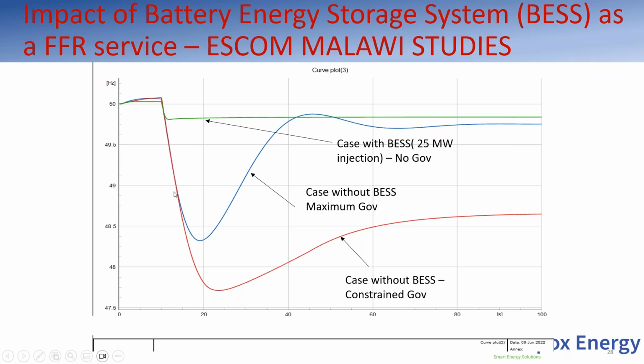But now with governing, the maximum governing here was around probably 40 megawatts, and the frequency went down to almost 48.5 for a big contingency in their grid. The contingency remains the same, so you can see the power of the battery - you don't need so much. The maximum governing here was around 40 megawatts, but with only 25 megawatts of battery, you get so much improvement.